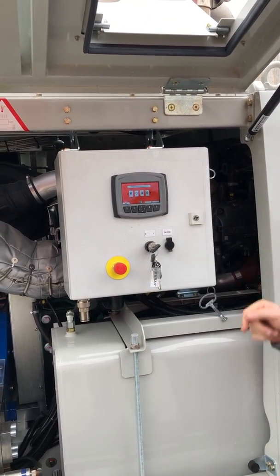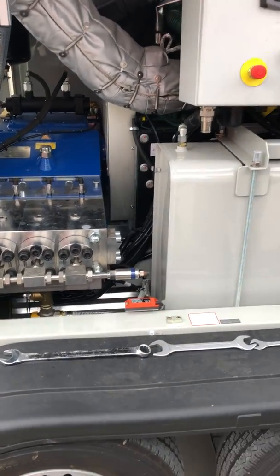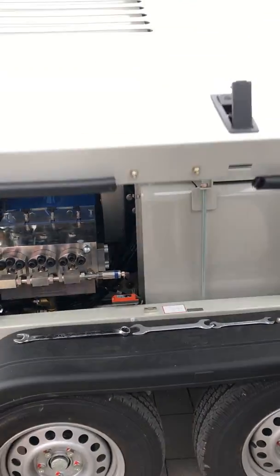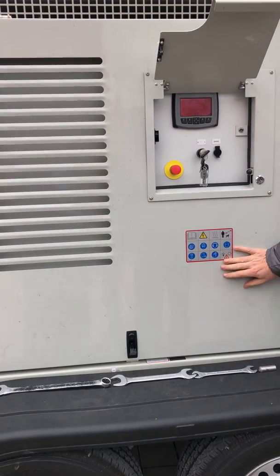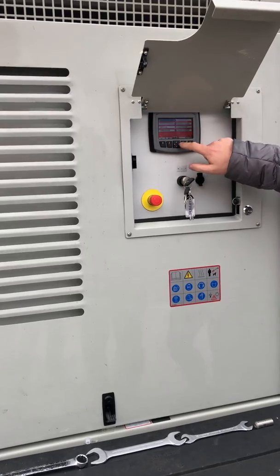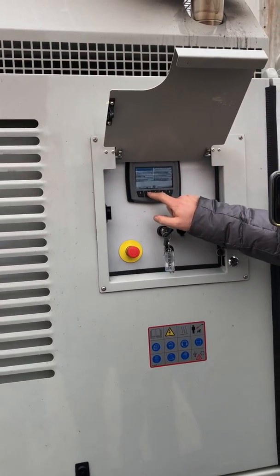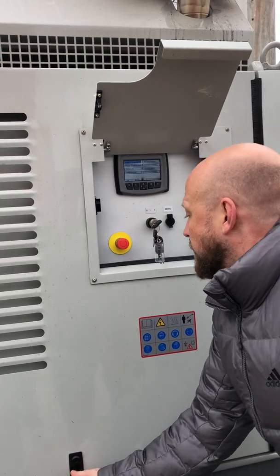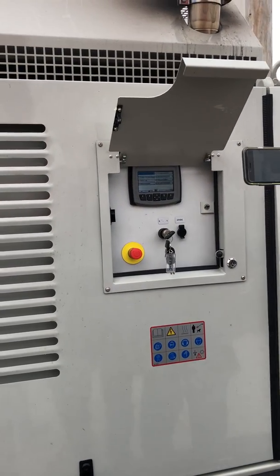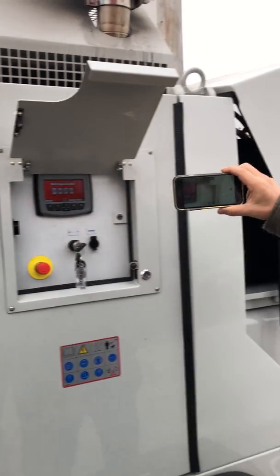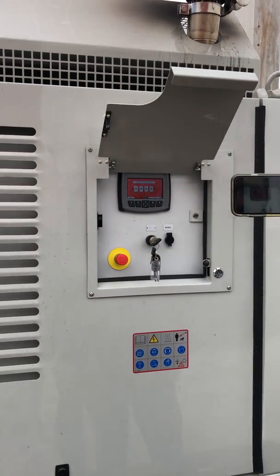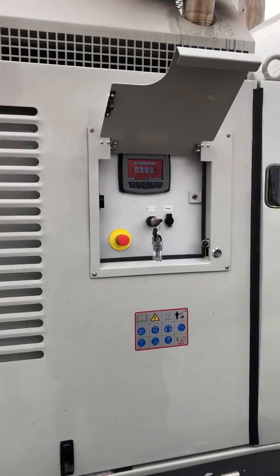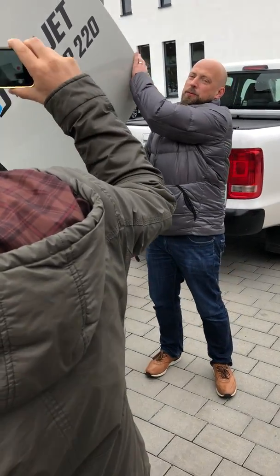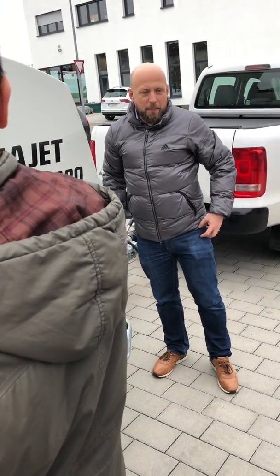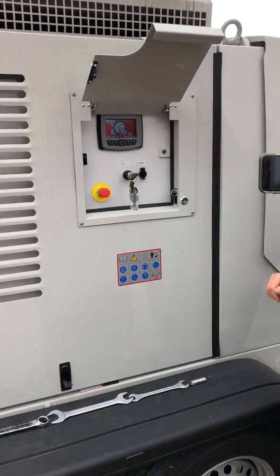So first of all, we have 3 cover switches on those doors. Whenever a door is open, this service mode comes up. When it's closed, you can work. When you open it up again, no matter which door you open, this comes back on. You just have to put in a code and you can work with the machine. This is for service personnel, so that you can work with 3 open hoods and you don't need 3 big magnets to short-circuit this.